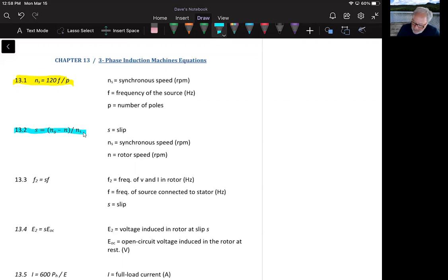The way that we would determine what the motor slip is, we would use something called a strobe tachometer, and we would physically determine what the rotor speed is and calculate what the synchronous speed is by knowing the number of motor poles and the frequency of the source. So, an example of something like this to determine what slip is, we can find in our textbook on page 274.